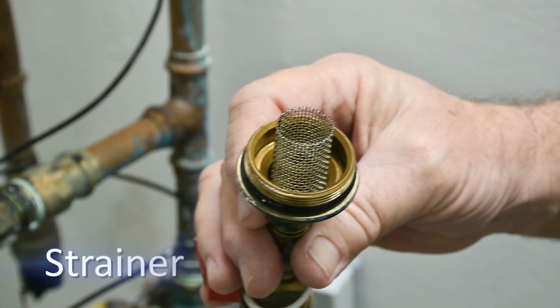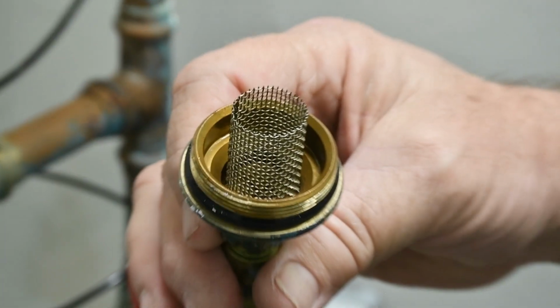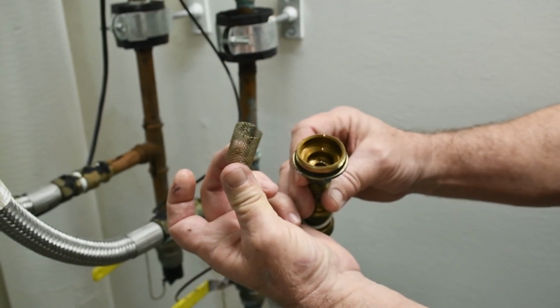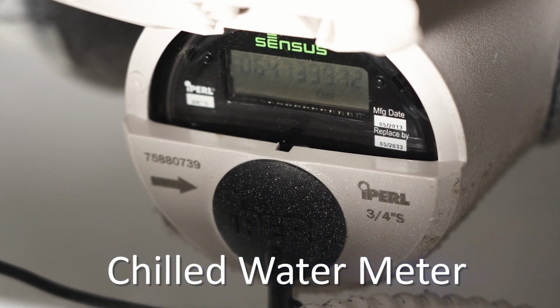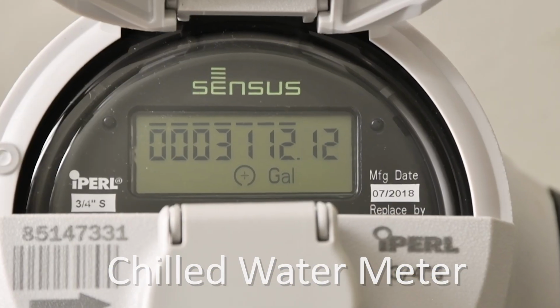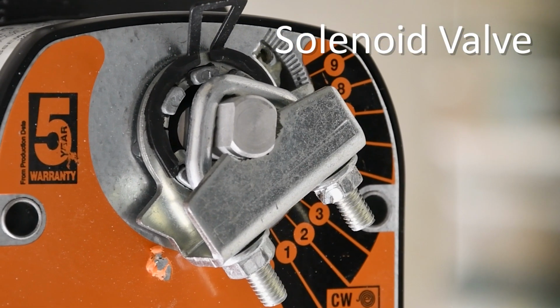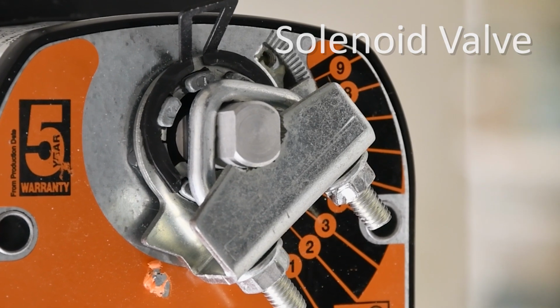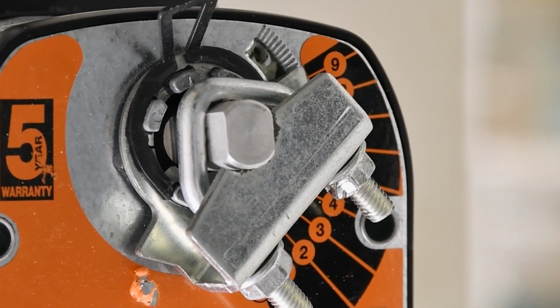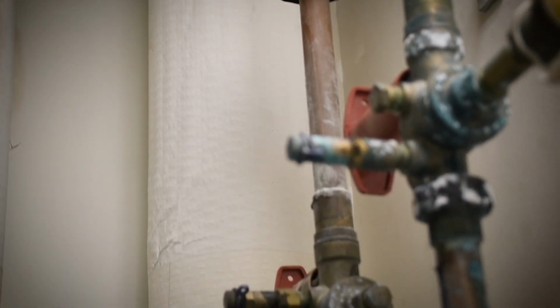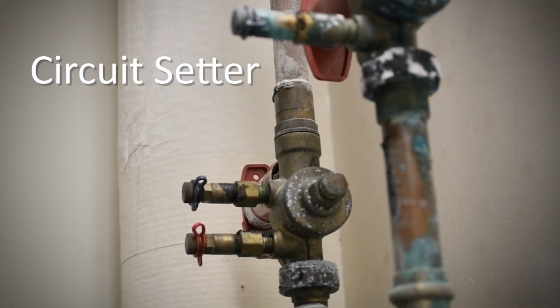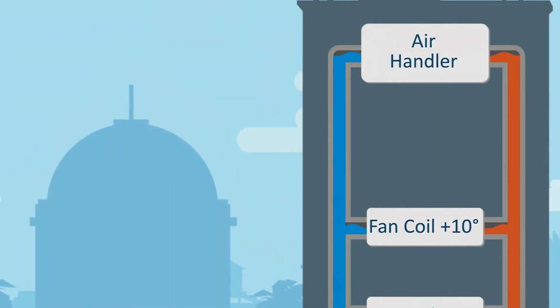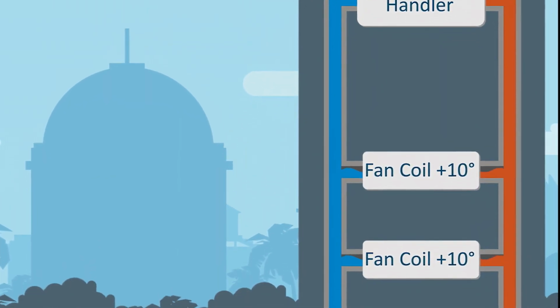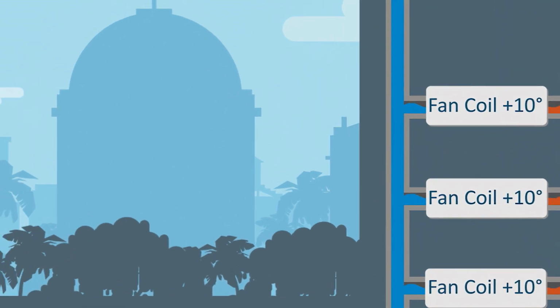The next component is a strainer, a small mesh basket designed to catch particles of dirt or debris that can damage the fan coil or the water meter. Next, the OUC chilled water meter can either be a brass-colored mechanical meter or electronic meter like this one. The solenoid valve, triggered by a signal from your thermostat, opens and closes to start and stop the flow of chilled water through the coil. Next, if available, a flow balancing valve, also known as a circuit setter, ensures your coil always receives the correct amount of chilled water, even when the system pressure changes due to high or low demand.